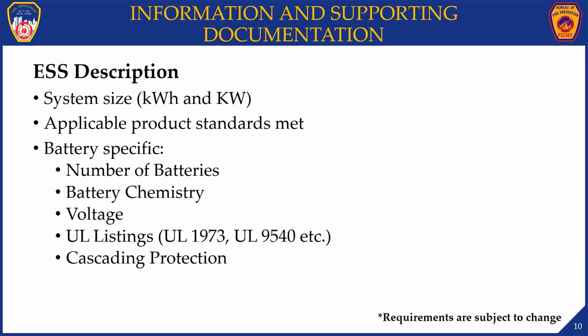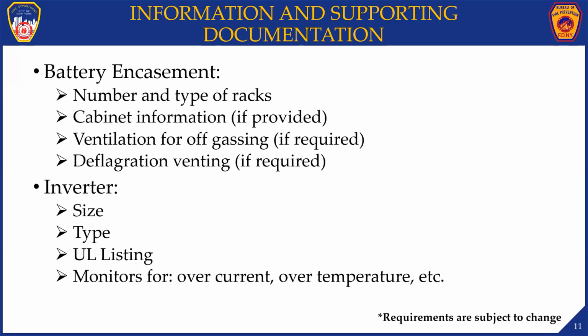For information related to the ESS itself, we want to see the system size, applicable product standards that are met, number of batteries in the system, battery chemistry of those cells, the voltage of those cells, UL listings, if there's any cascading protection, the number and types of racks in the enclosure, ventilation system if required, deflagration venting if required. For information related to the inverter, we want to see the size, type, and the listing for the inverter, what the inverter monitors, any protection measures that are built into the inverter.